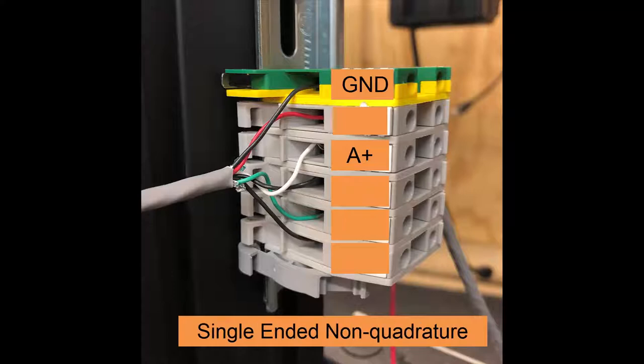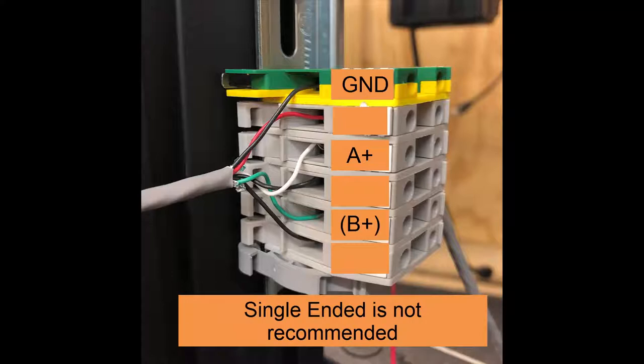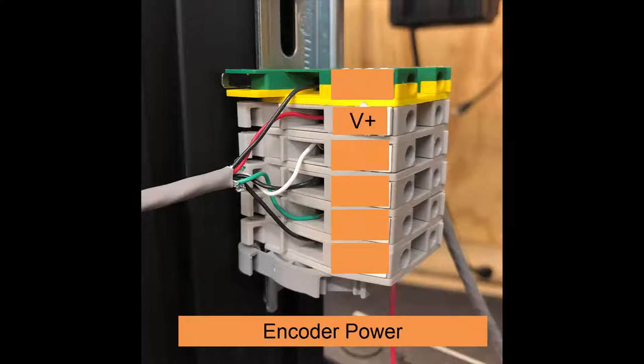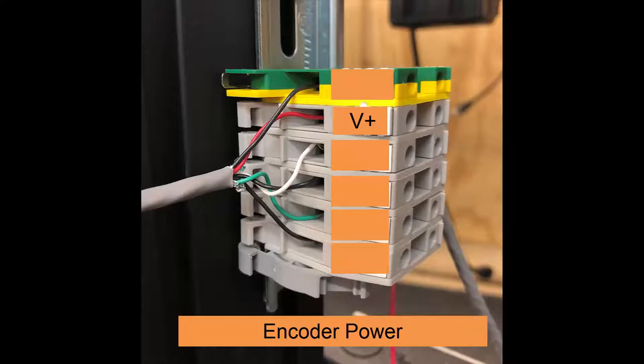The ground wire is the black wire in the red-black twisted pair. However, using this signal type is generally not recommended because of its susceptibility to noise. You will only wire the ground wire if you want a single-ended signal. You will only use the power wire, which is the red wire from the red-black twisted pair, if the gauge will be powering the encoder, as is the case with an encoder wheel. Most often, when using a flying leads cable, the encoder is powered by another power source. In this case, do not wire the red flying lead wire, as this can damage the electronics inside the gauge.